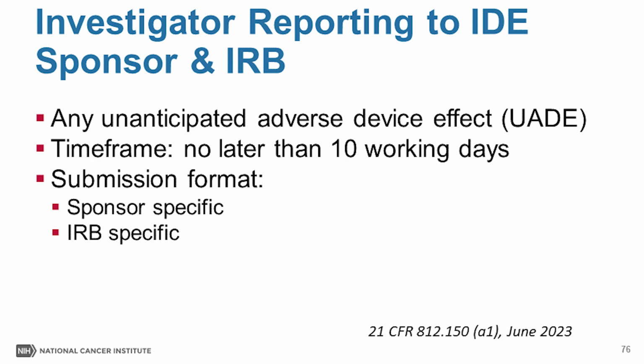An investigator needs to submit to the IDE sponsor and to the reviewing IRB or the IRB of record any unanticipated adverse device effect occurring during the investigation, as soon as possible, but no later than 10 working days after the investigator learns about the effect. So again, refer to the sponsor as well as to the IRB in terms of the submission formats.